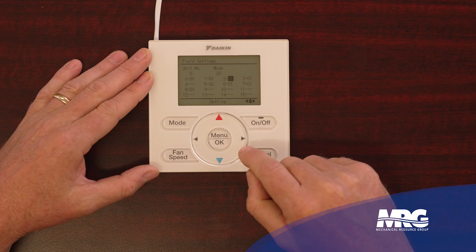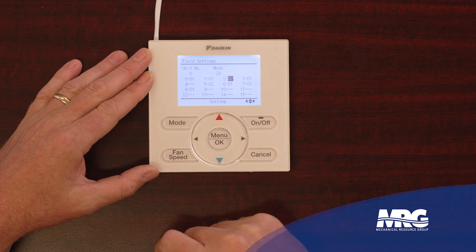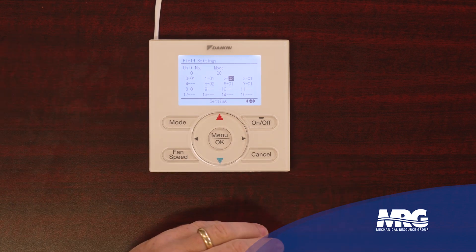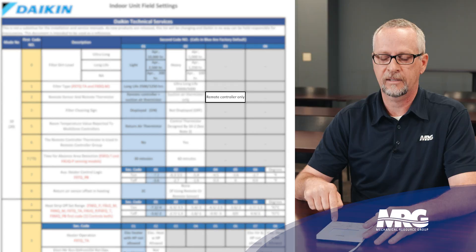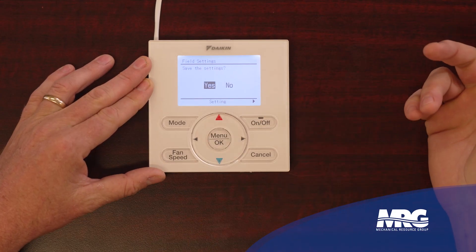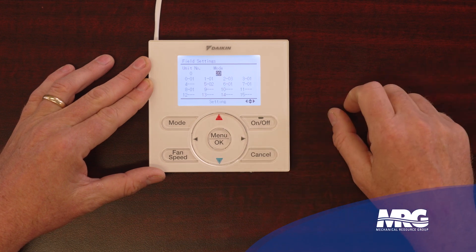So now we want to change it and tell it to use the NAVSTAT. Mode 2-02 says the unit return air thermistor is primary and the NAVSTAT is out of the picture completely. Mode 2-03 tells it the thermistor in the NAVSTAT is primary — it does not look at any other thermistor, it will only control to this — which is what we're used to here in the states. You go into any residential home, the temperature displayed on the thermostat is the temperature the unit is controlling to, and that's what we're doing here. This will save you a lot of callbacks when you do your setup. Select it, select OK, it's going to ask you if you want to save that setting — yes, save it. Now I could continue to make more changes, or I could just back out, and it's going to save my setting and go back to my home screen. My unit is now going to control to this room temperature off of this thermistor.